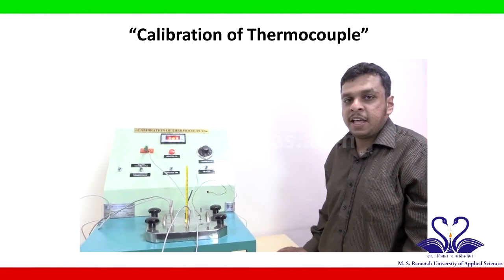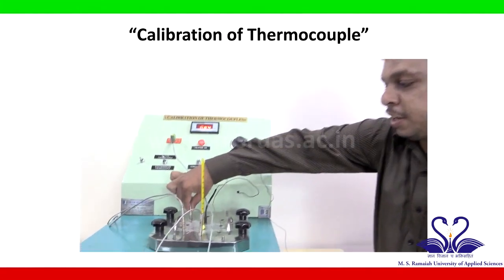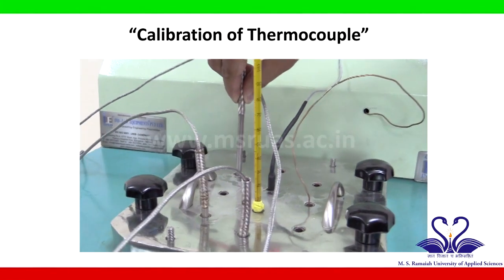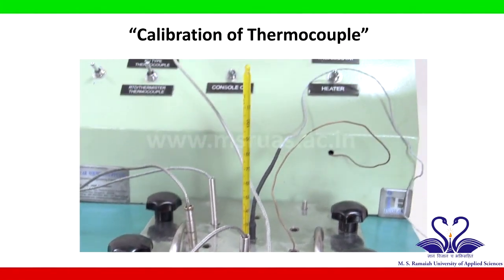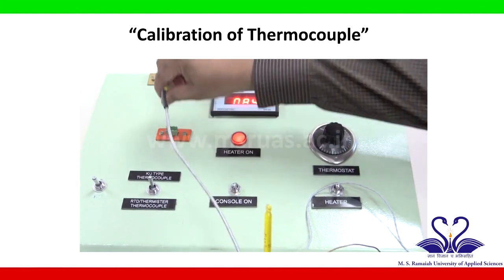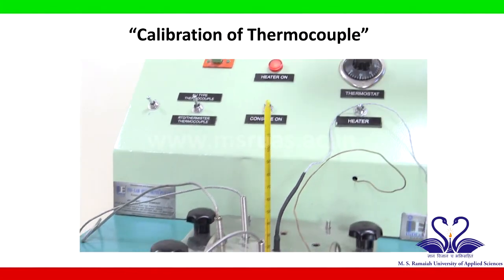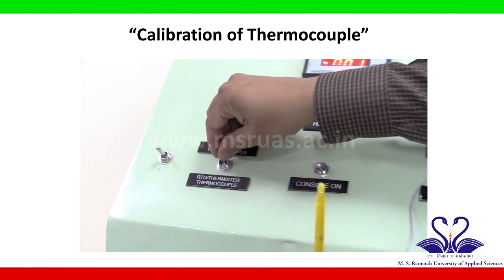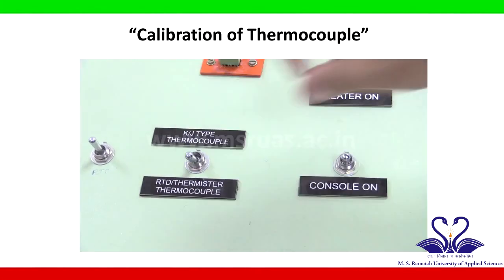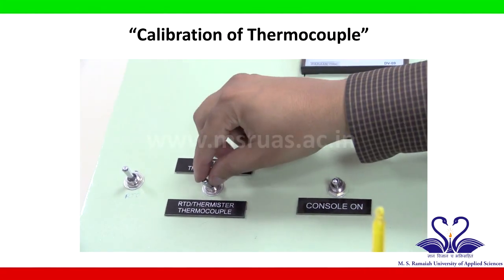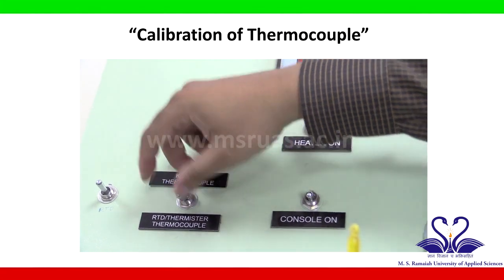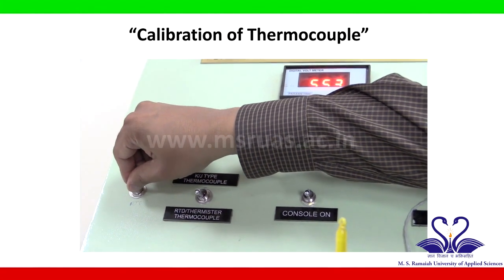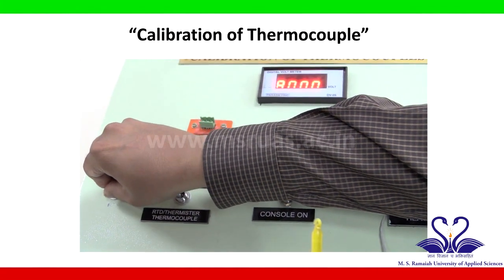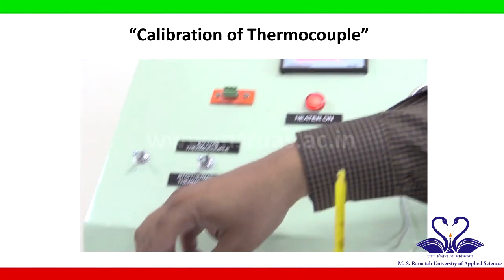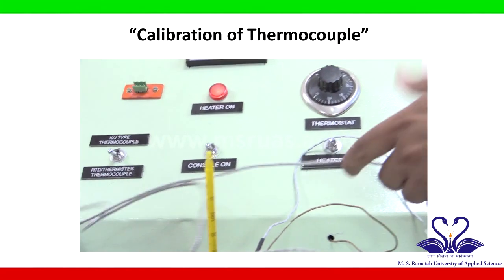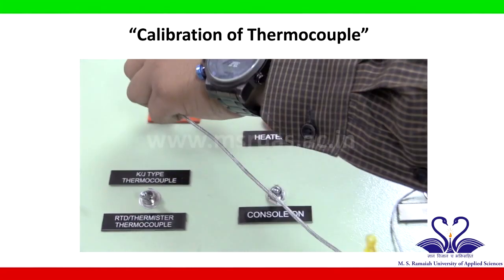Next, we will be calibrating resistance temperature detectors, which are also known as RTDs. This is the RTD. Before we connect the RTD, we have to ensure that the J-type thermocouple is disconnected and the setup mode is changed to RTD or thermistor mode. Once you have brought this to RTD or thermistor mode, it is important to bring it to completely RTD mode by bringing this switch down. Now connect the RTD switch similarly as connected J-type and K-type thermocouple.